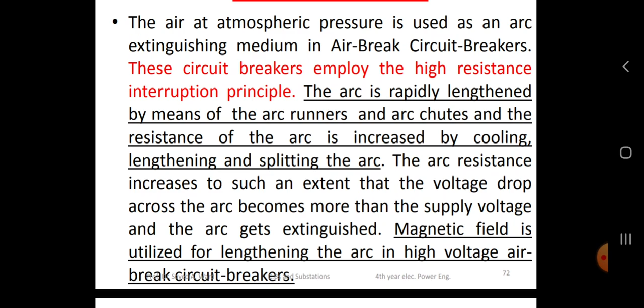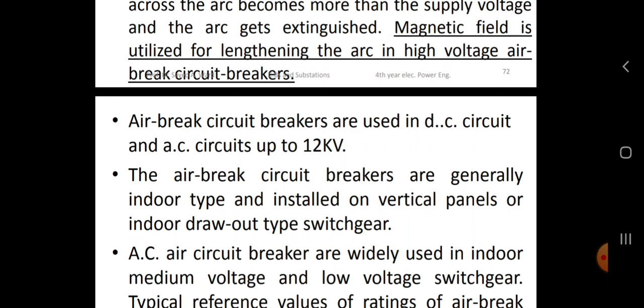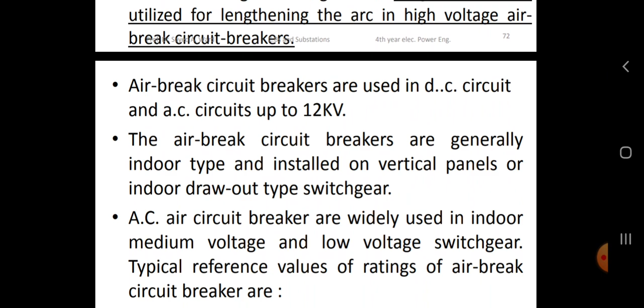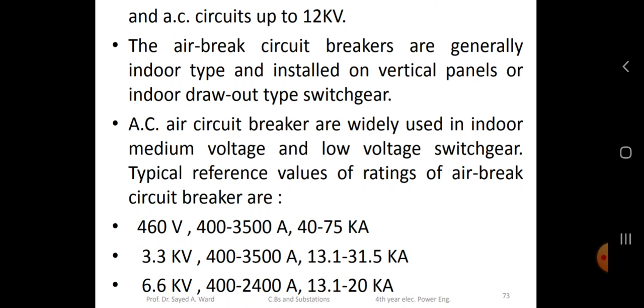The air break circuit breakers are generally indoor types and installed on vertical panels or as indoor draw out type switchgear. AC circuit breakers are widely used in indoor medium voltage and low voltage switchgears. Typically, reference values of the rating of the air break circuit breakers are 460 volt, 3.3 kV, and 6.6 kV.